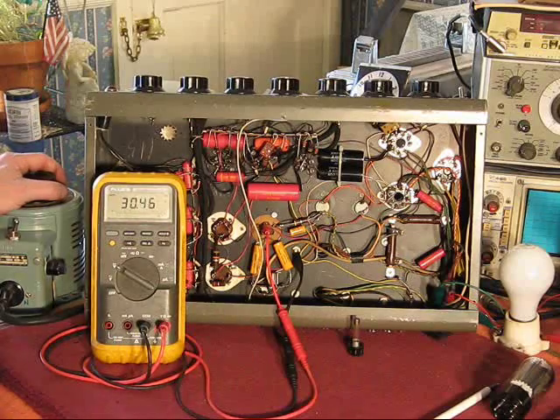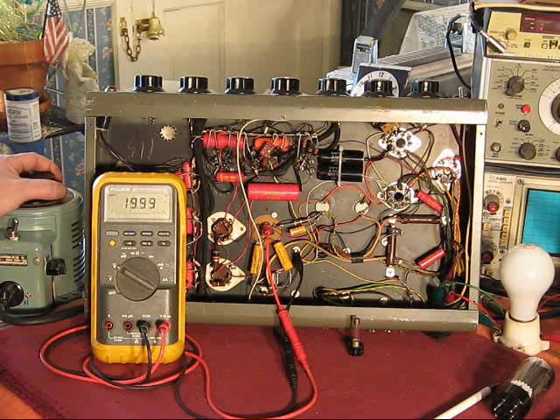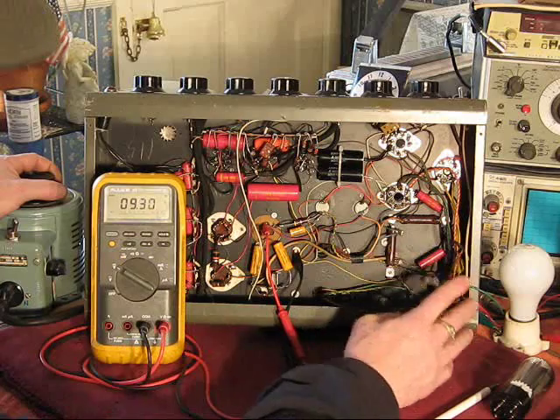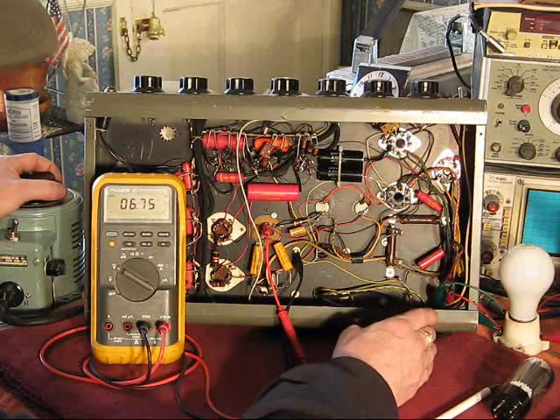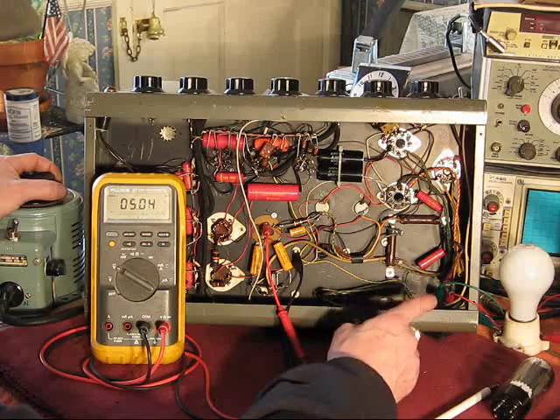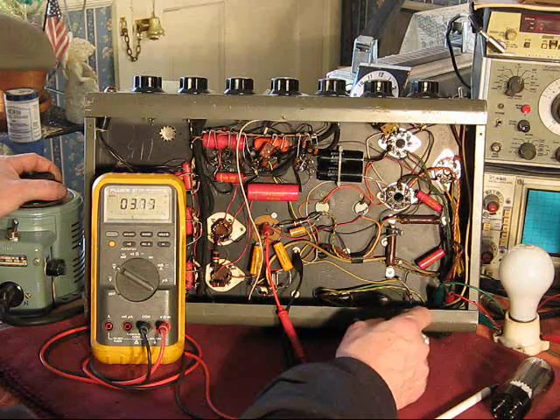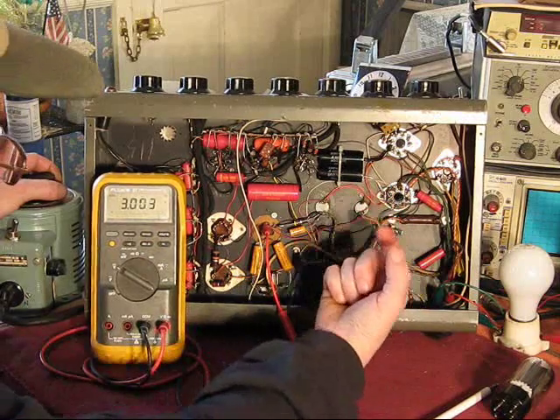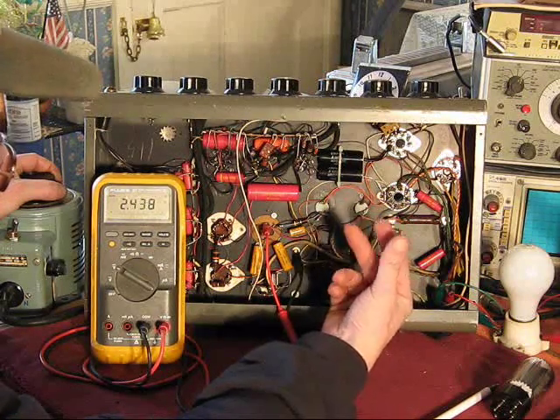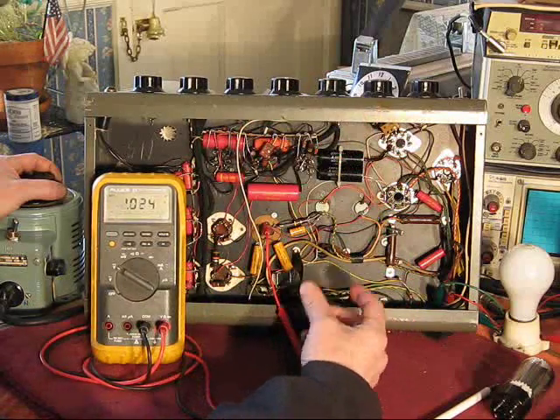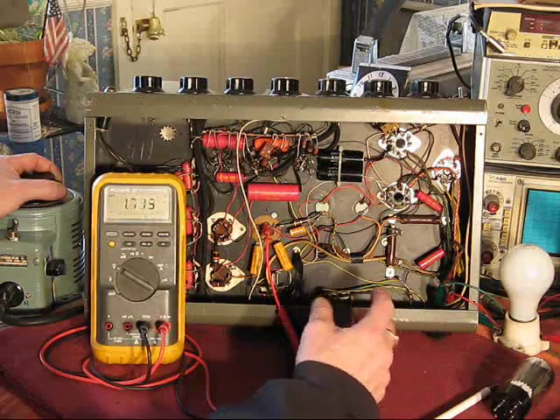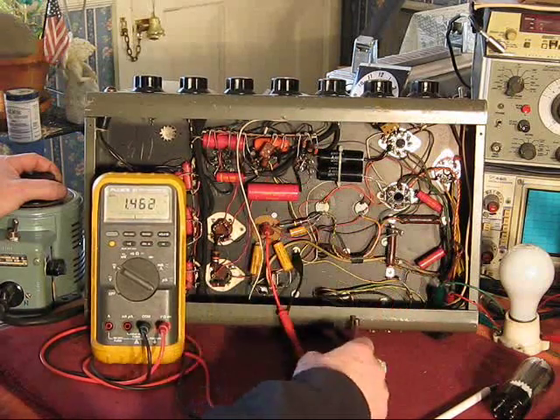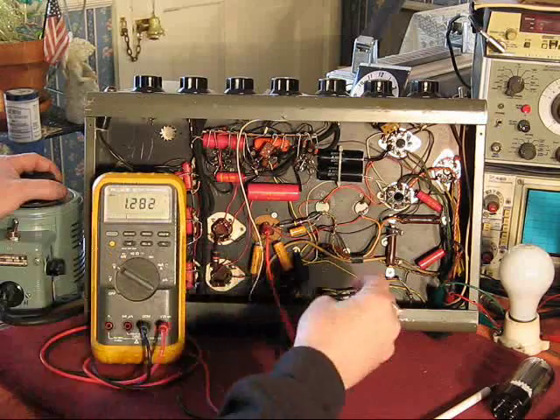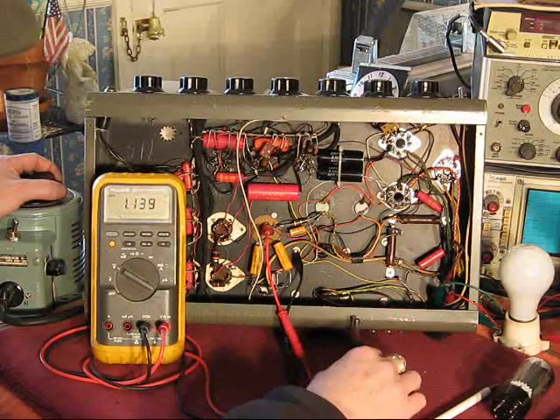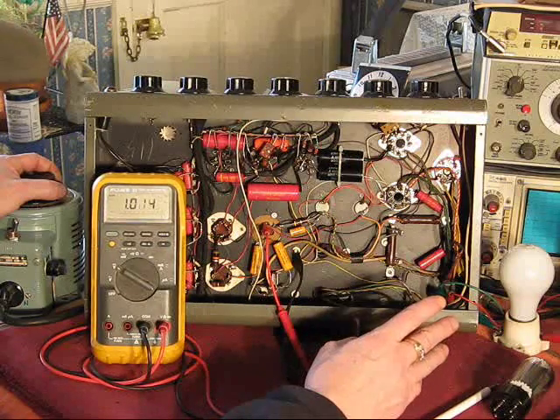If you don't have a variac, you can just use a ballast lamp in series with the line. It can work for you, but if you're going to do that, I suggest starting off with a very, very low wattage lamp, maybe even a 7-watt lamp like a night light, and work your way up from that - go to 7, then maybe a 25-watt bulb, then a 40, then a 60, like that. If there's a major problem, it will prevent catastrophe doing it that way.